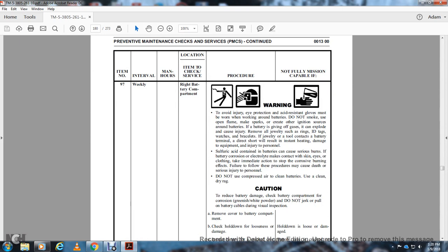Item 97, weekly, right battery compartment. Warning: to avoid injury, eye protection and acid-resistant gloves must be worn when working around batteries. Do not smoke or use open flames, and do not make sparks or create other ignition sources around the battery. If the battery is giving off gas, it can explode and cause injury. Remove all jewelry, such as ID tags and watches. Jewelry can contact the battery terminal and cause a direct short, which results in instant heating, damage to the equipment and injury to personnel. Sulfuric acid contained in batteries can cause serious burns. Battery corrosion electrolyte can contact skin, eyes and clothing. Take immediate action to stop the corrosive burning effect.